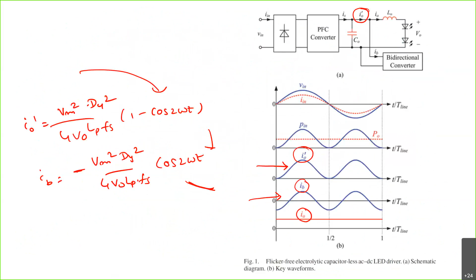Generally it develops a second order harmonic. To filter out the second order harmonic, you require a large filter, which may be an electrolytic filter. But if you keep an electrolytic capacitor, its life expectancy is very small, just simply 5,000 hours or so. When it is operating at higher temperature, the capacitance will be lost. Therefore, we need to remove that electrolytic capacitor. Remember, we are not removing the capacitor; we are just choosing a better, smaller capacitor, whose life will be much higher than the electrolytic capacitor.